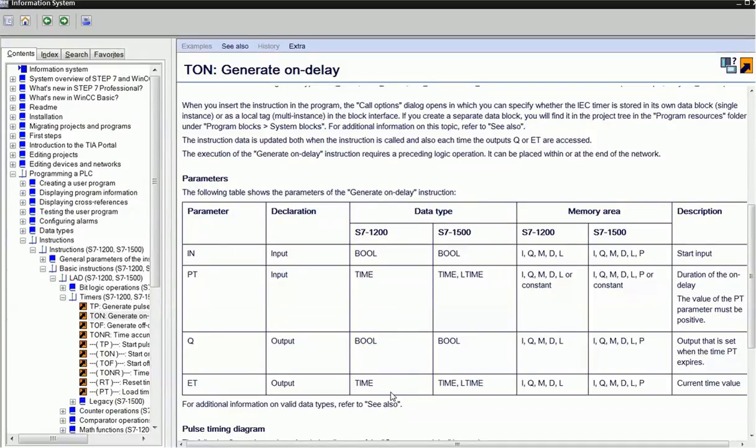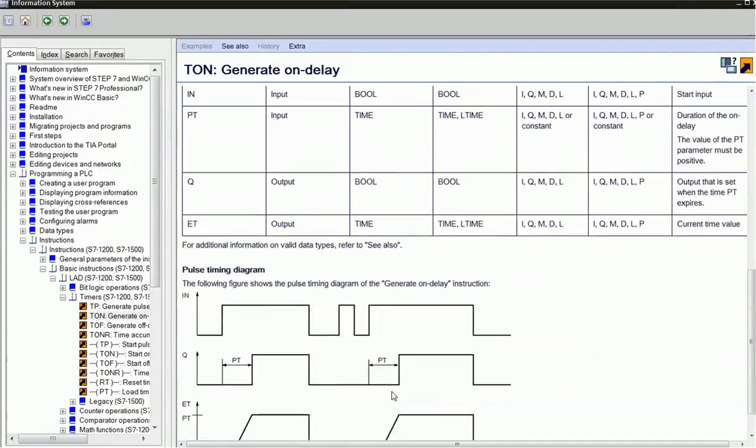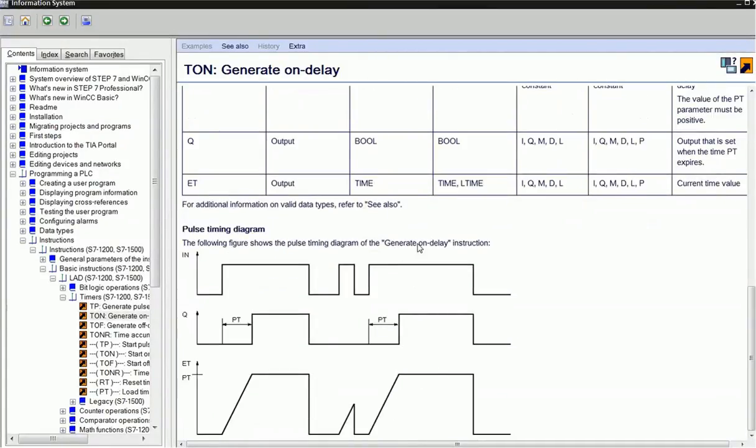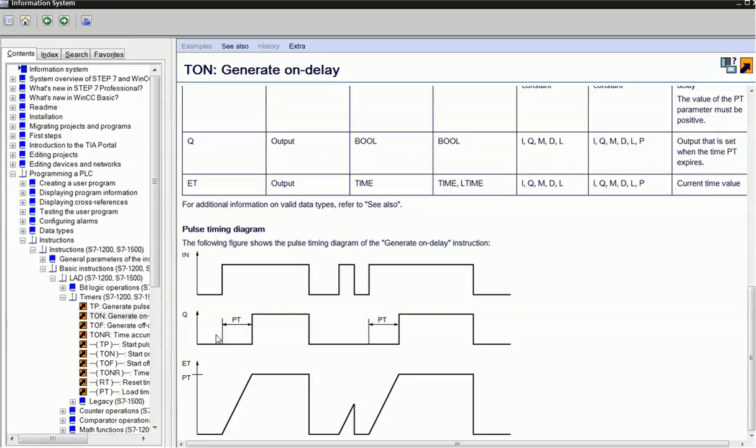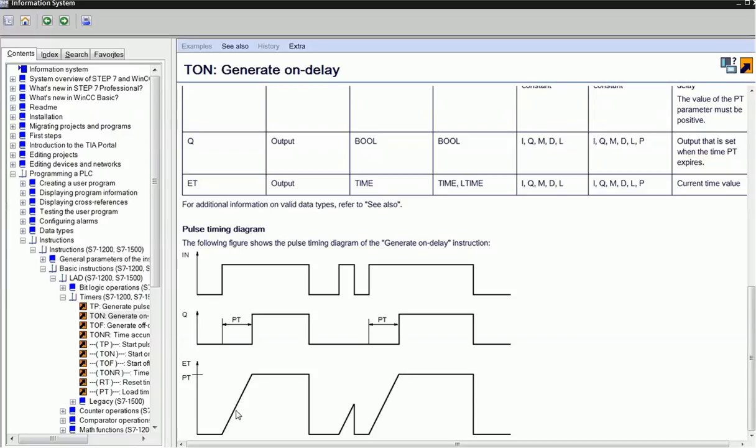This shows the timing diagram with input, output, elapsed time, and preset time. When I give a high signal at the input, the timer will start to count the time. It will increase the time up to the preset time we've given, and after this preset time, the output will be on.